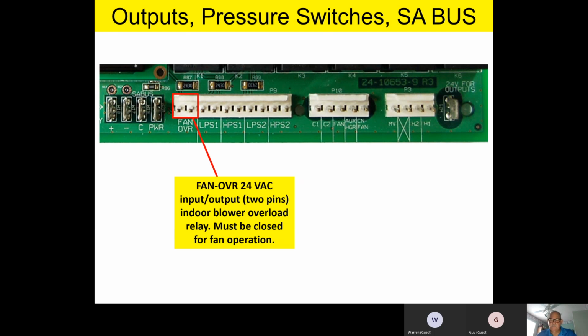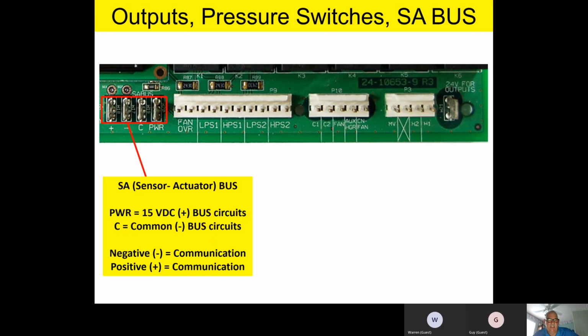Okay. Right next to the fan overload, you're going to have an SA bus. Now, this SA bus is going to be 4 hard terminals, and those terminals are going to be positive and negative, C for common, and power. The positive and negative, the plus and minus, are communicating terminals. If you have something on the SA bus, whether it's an economizer or your MAP device hooked up by that little 6-pin plug, which we'll show you in a minute, which is just a parallel port on that SA bus, the positive and negative are communication terminals. And then the power terminal, the PWR, is a 15-volt DC plus polarity for bus circuits. The C is 24-volt common, which is basically a negative, or it pulls it to 0.